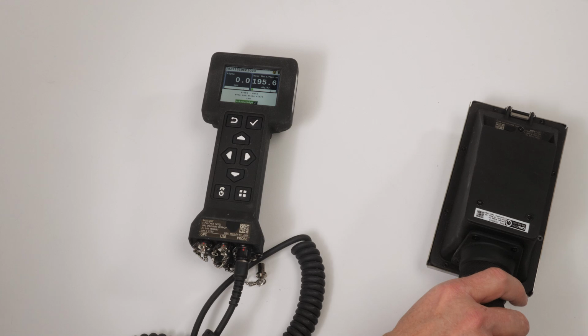If the alpha channel counts are higher than 90 counts per minute, the beta channel counts are not accurate. To take an accurate beta measurement in such circumstances, place a piece of paper between the alpha-beta probe and the contaminated surface. Do not let the probe face come in contact with what is being surveyed, as this could lead to puncture of the mylar window or contamination of the probe face. There is a metal grate and then a protective mesh screen in place to protect the mylar window. This window is very thin and can be damaged easily if the probe is not handled with care.